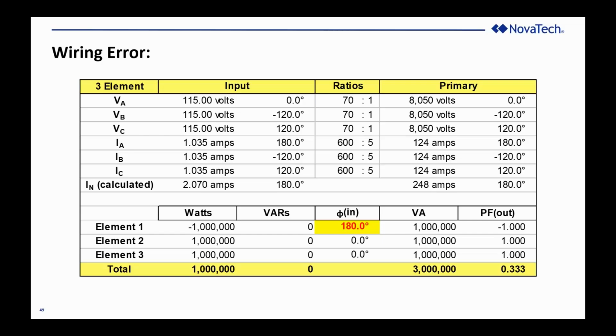So I can see 0, minus 120, and plus 120 as my 3-phase voltages, phase to neutral voltages. And on the phase to neutral current, I see the B and the C are correct, minus 120 and plus 120, just like the voltage. But on the A phase current, I have a 180-degree phase shift.